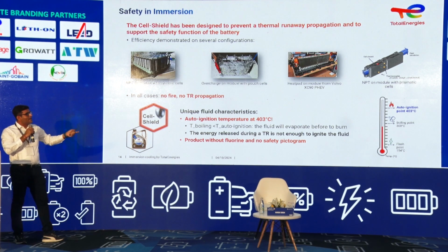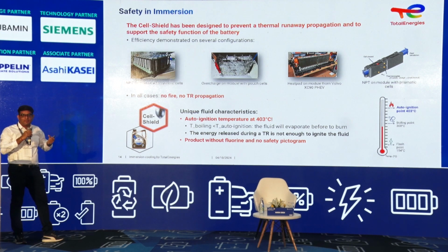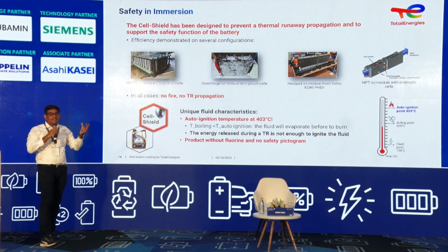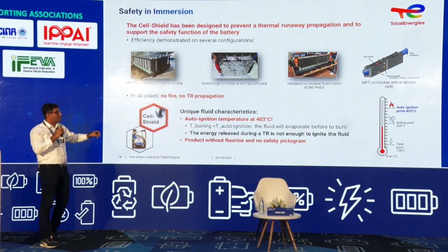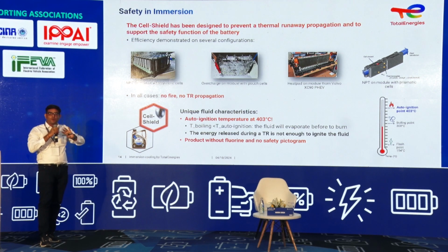It's also interesting to note that the boiling point is lower than the auto-ignition temperature. So when fire catches inside the battery, the boiling point is reached first and the fluid evaporates. Once it evaporates, it condenses and takes all the heat, so there is no probability or risk of fire at all.